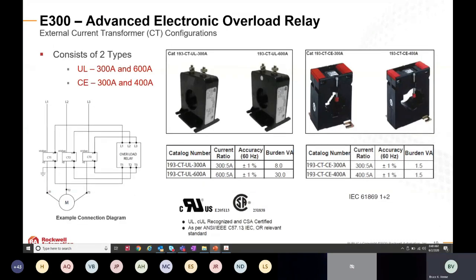As I mentioned, for the external CT configurations, the E300 does have its own set of external CTs that you can leverage that are certified to either UL or CE standards. And you can see on the bottom left there an example image of a connection diagram of how you would deploy this in an external CT fashion. These are just some offerings that are offered alongside the E300. You can use additional CTs or third-party CTs as long as you are mindful of that 5 amp secondary on the current ratio there. But again, if you're looking to get everything from Rockwell, there is an offering here that is supported.